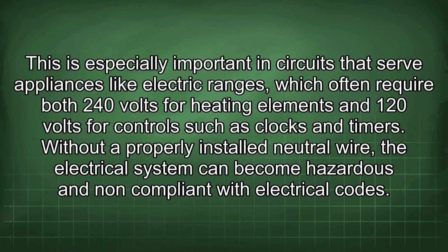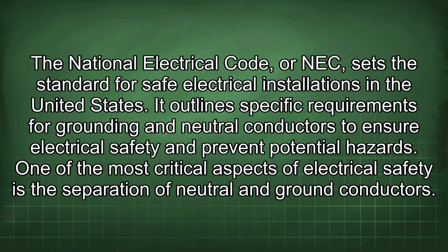Without a properly installed neutral wire, the electrical system can become hazardous and non-compliant with electrical codes. The National Electrical Code, or NEC, sets the standard for safe electrical installations in the United States. It outlines specific requirements for grounding and neutral conductors to ensure electrical safety and prevent potential hazards.